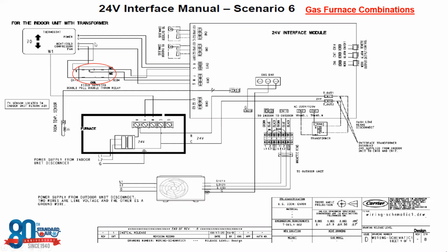Now you'll notice on here, we set this up as a dual fuel, and we have a W1 terminal right here. This W1 terminal comes directly from the thermostat and then feeds into the W terminal on the gas furnace. This is going to be the output for turning on the gas heat. And this is where that dual fuel operation comes in. Okay, and you can set this if you want the heat pump to shut off when it's 32 degrees outside and then kick over to the gas furnace.